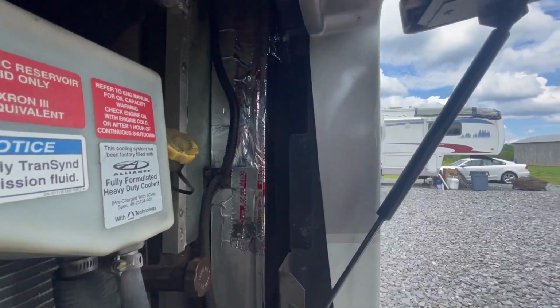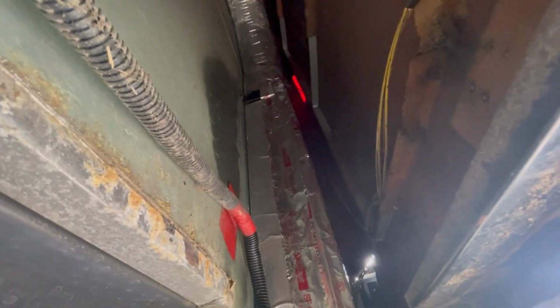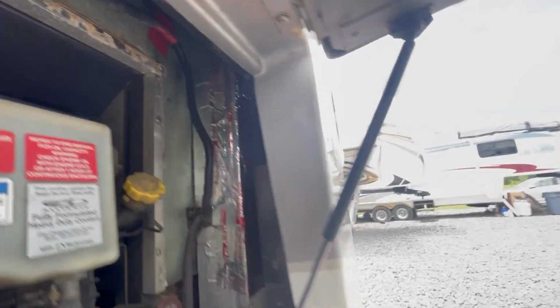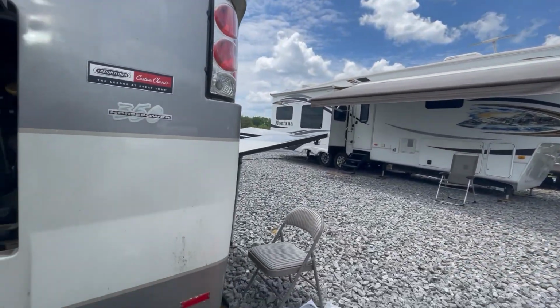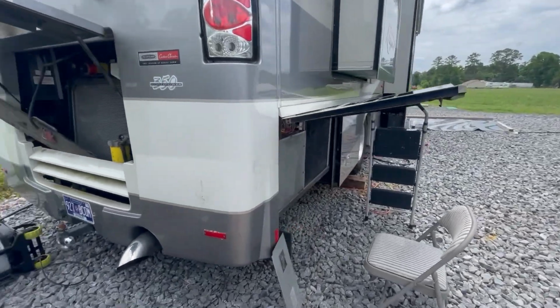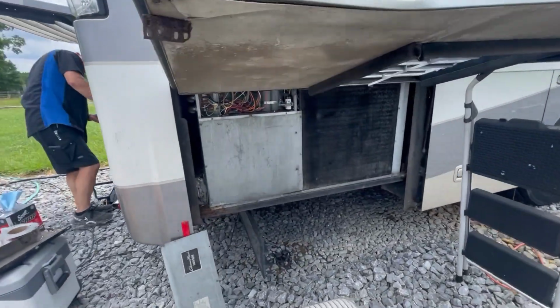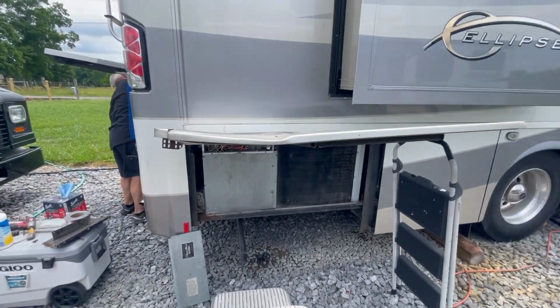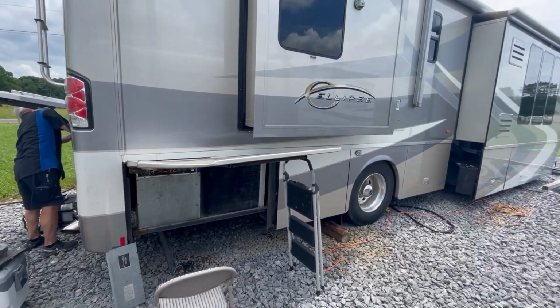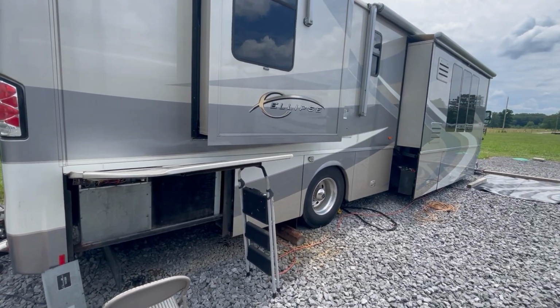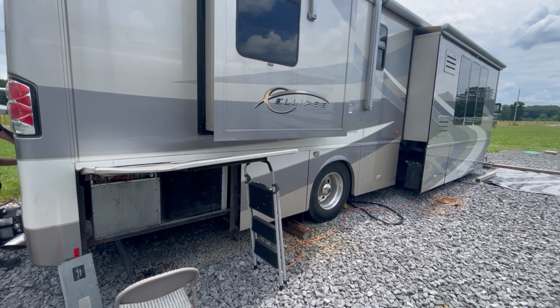Okay, so we've got all this now taped up, and as you can see, that's all held together good now with that mastic tape. That's about the only way to fix that. But we do have good amp draw on the compressors now, so we're good on that. We got him all fixed up, and we're going to test the grill up front, but we're almost 90% sure that was the solution.